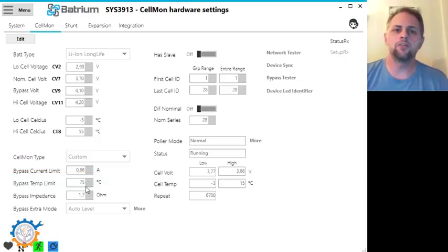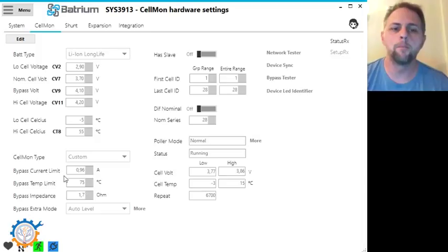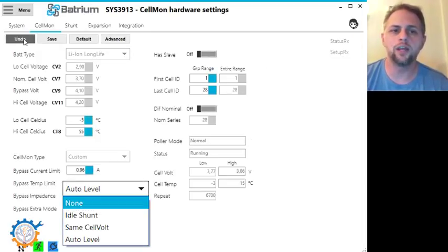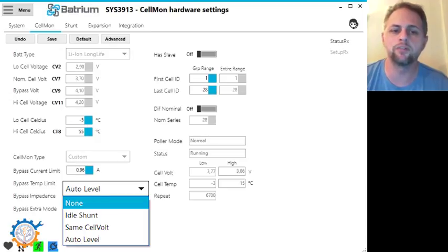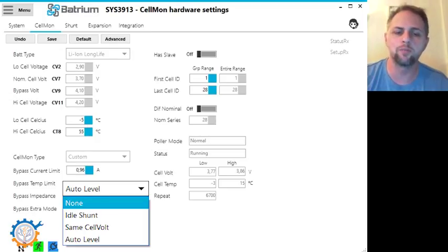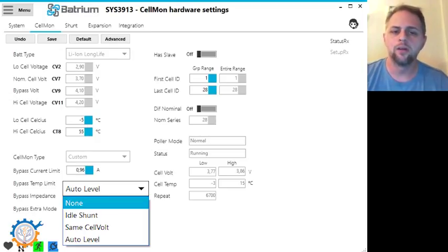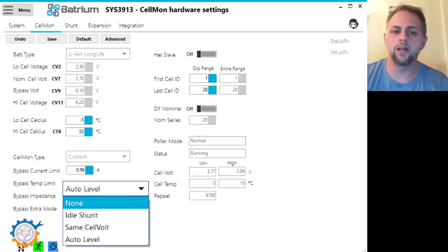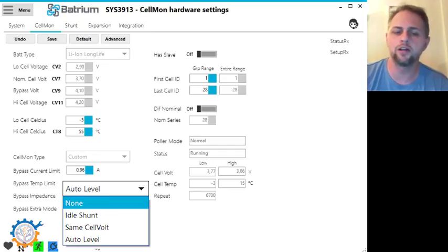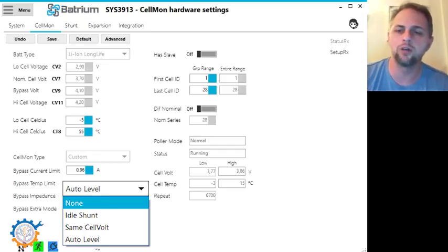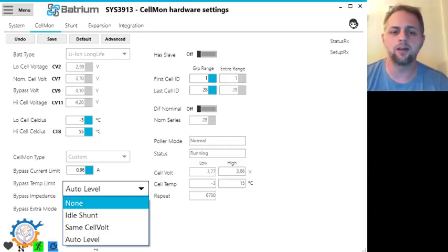In the Batrium software you have a couple of more bypass modes enabled. If you go to edit, you are able to actually go into the bypass extra mode. Normally it's set to none, and then you have the idle shunt, you have the Same CellVolt, and you have the auto level. What I'm going to go through today is the auto level functionality.